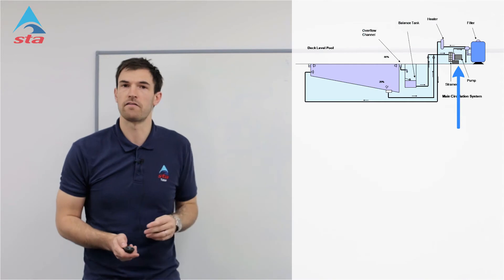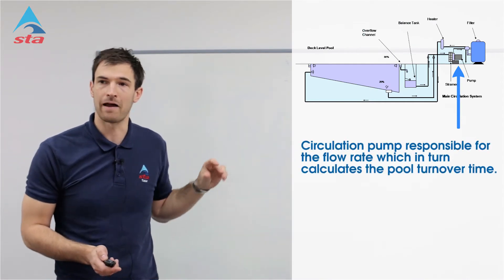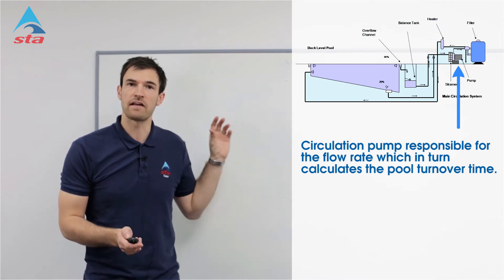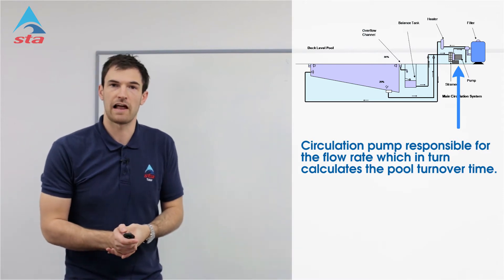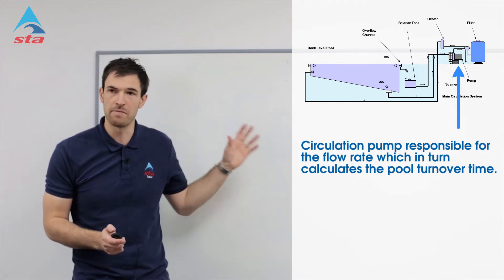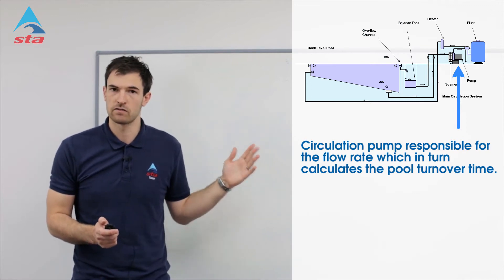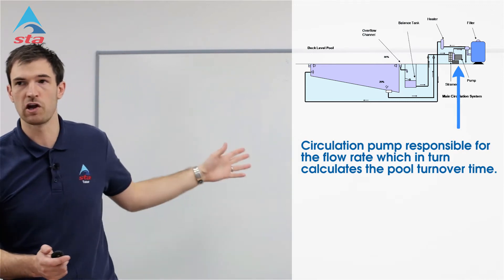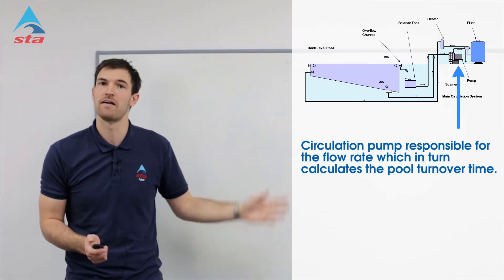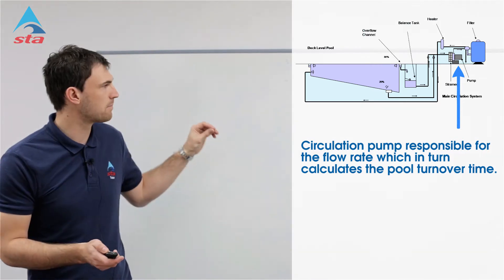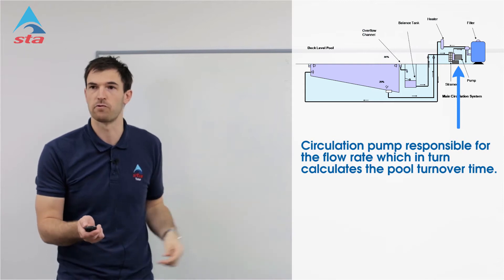Looking at the basic schematic of a swimming pool, you've got your water flow coming from your balance tank, from your sumps, and then that's going into your pump. Your pump is integral to the circulation rate — it determines the flow rate, the speed of water, the volume, and the turnover time. So if that pool is sitting at 300 cubic metres and you've got a 150 cubic metres per hour flow rate, that's a two-hour turnover time. That's an important element that's going to affect the filtration velocity, the speed downwards through the filter.